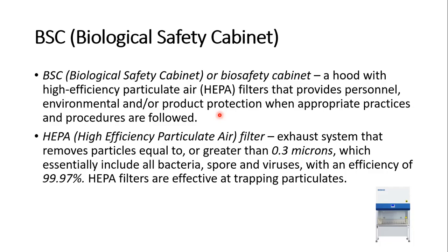HEPA is an acronym that stands for High Efficiency Particulate Air Filter. It is an exhaust system that removes particles equal to or greater than 0.3 microns, which essentially include all bacteria, spores, and viruses, with an efficiency of 99.97%. HEPA filters are effective at trapping particulates. HEPA filter is a form of air filter that filters out those microorganisms with more than 0.3 microns in size.